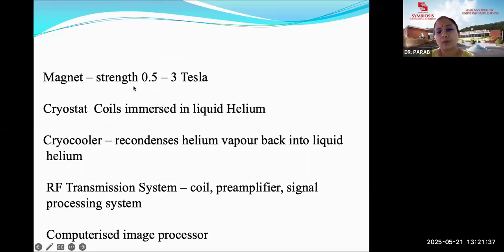These coils which we spoke about are basically immersed in liquid helium. And here we have a really big challenge, because this liquid helium recondenses. So basically there is a cryo cooler. This cryo cooler condenses the helium vapor. Helium is a gas, right? So it condenses the helium vapor into liquid helium, and in that liquid helium, the cryostat coils are immersed. So the challenge here is to keep the liquid helium in the liquid state all the time.